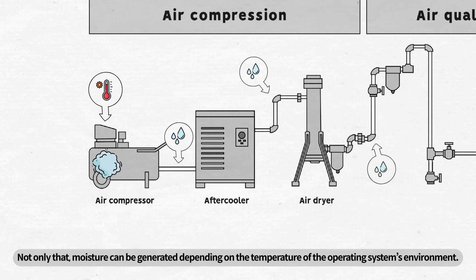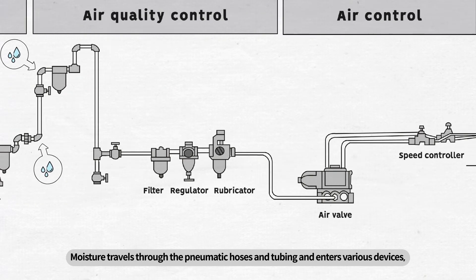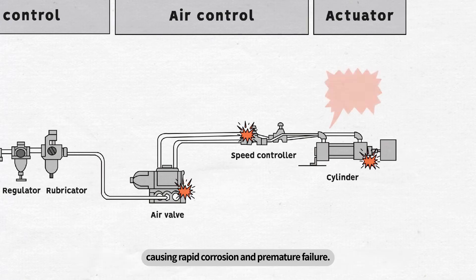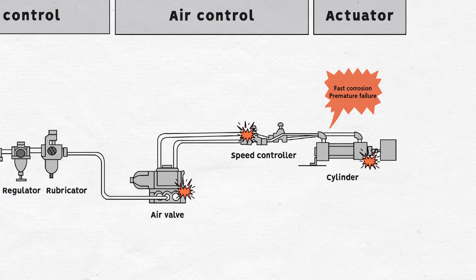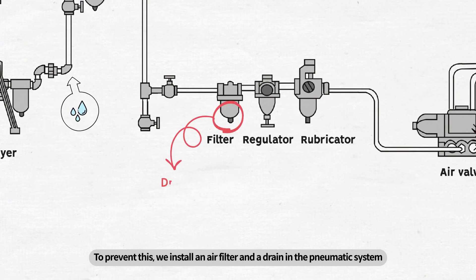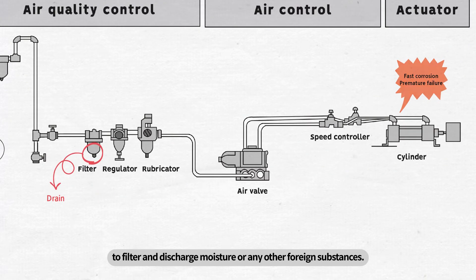Not only that, moisture can be generated depending on the temperature of the operating system's environment. Moisture travels through the pneumatic hoses and tubing and enters various devices, causing rapid corrosion and premature failure. To prevent this, we install an air filter and a drain in the pneumatic system to filter and discharge moisture or any other foreign substances.